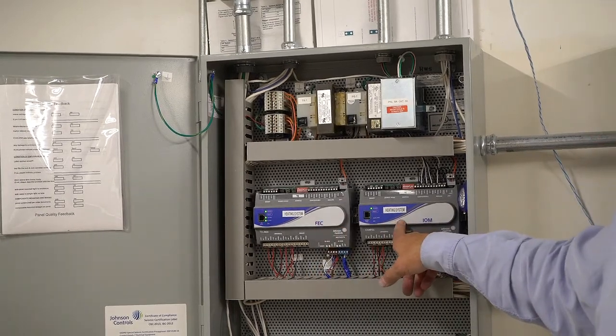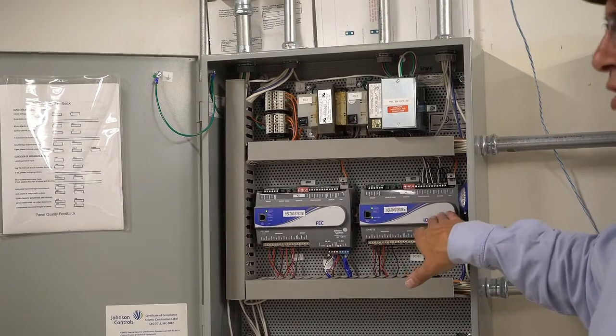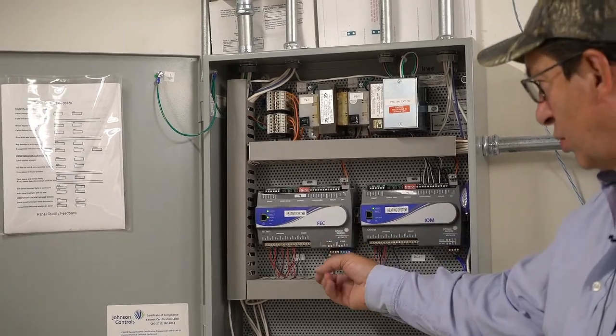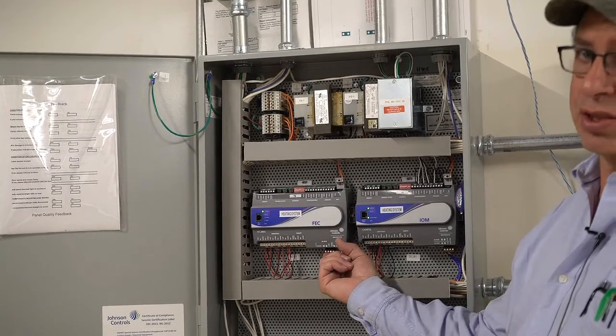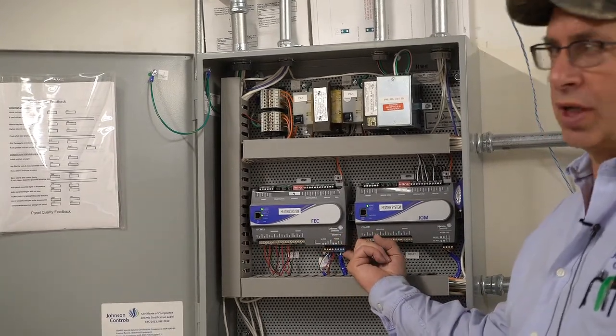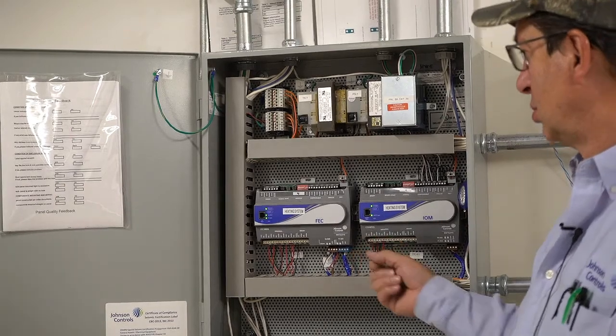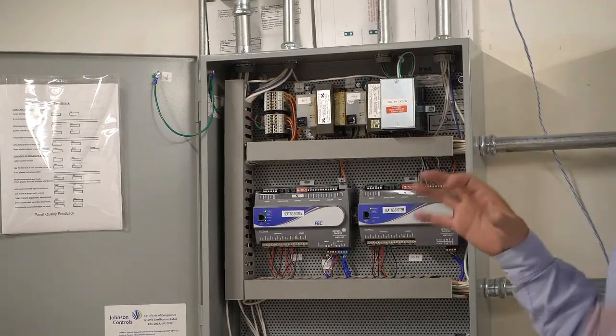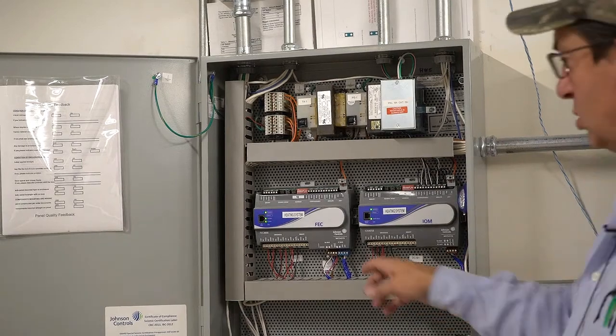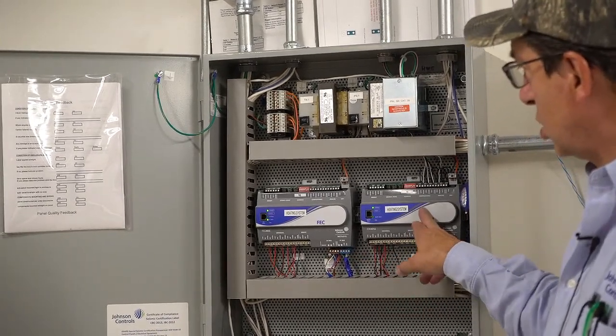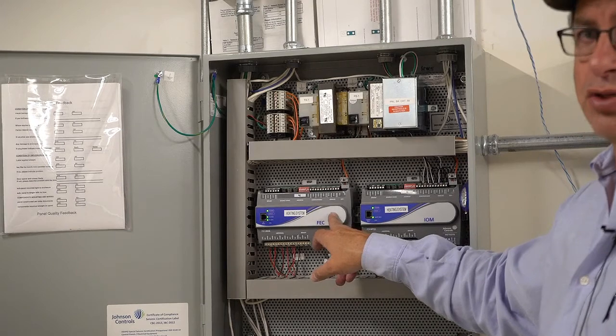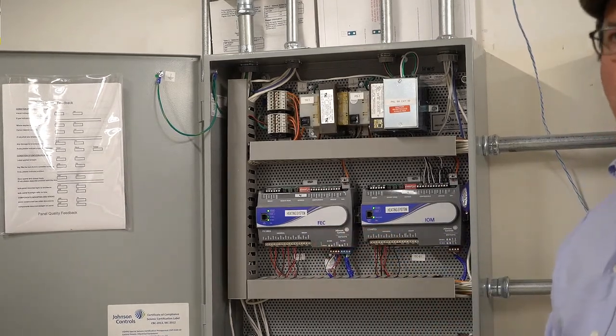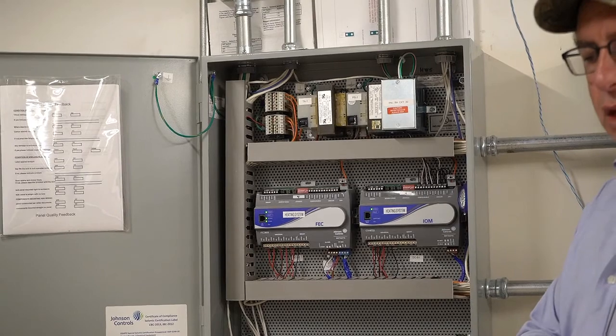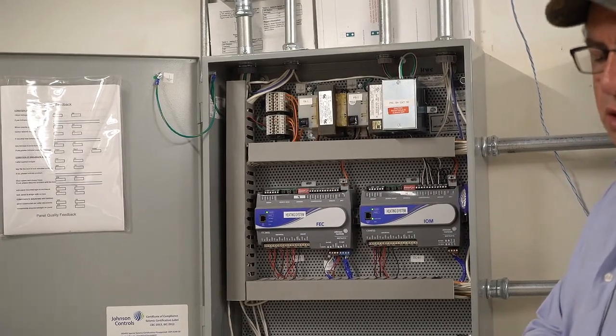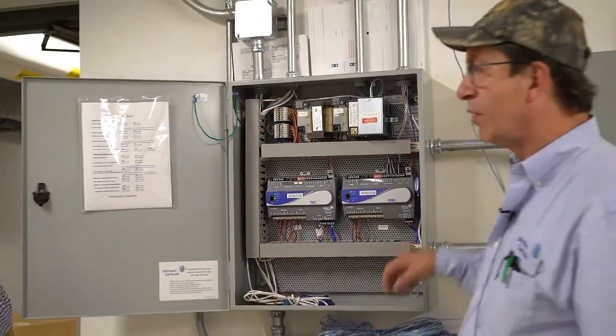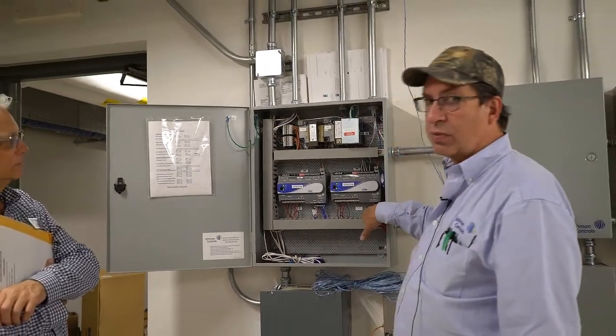This unit tells this one what to do. These units are connected to this unit through this brown plug, which is an SA bus. This is different than the blue plug, which is our field trunk. The field trunk daisy chains to all the systems that have brains. The brown SA ties these IOMs into our FEC controllers. And all of our thermostats that we went through, like the ones in the administration office, the fan coil 9 in the gift shop, they all daisy chain back into this FC bus also.